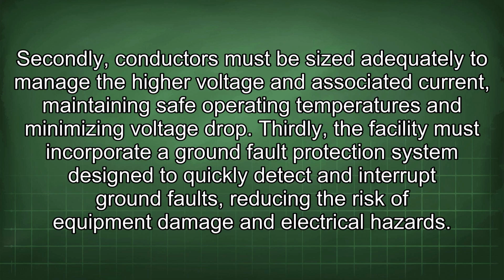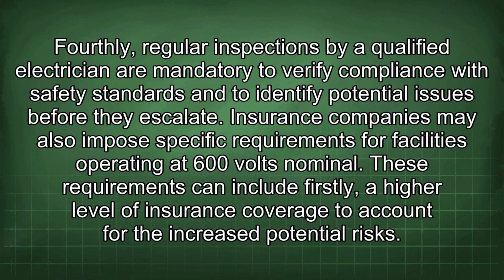voltage drop. Thirdly, the facility must incorporate a ground fault protection system designed to quickly detect and interrupt ground faults, reducing the risk of equipment damage and electrical hazards. Fourthly, regular inspections by a qualified electrician are mandatory to verify compliance with safety standards and to identify potential issues before they escalate. Insurance companies may also impose specific requirements for facilities operating at 600 volts nominal.